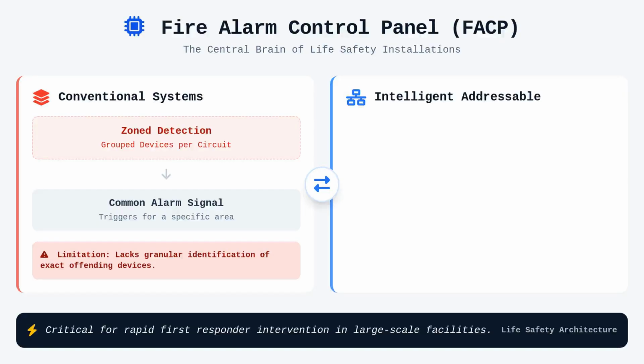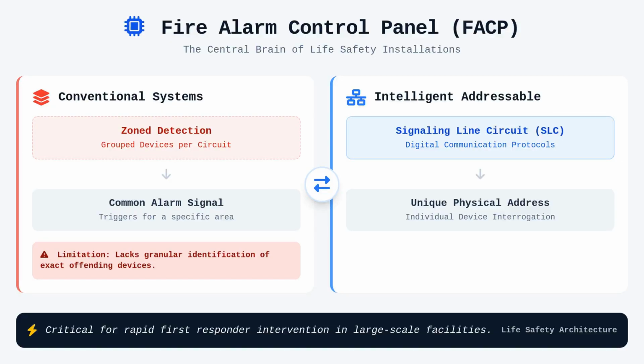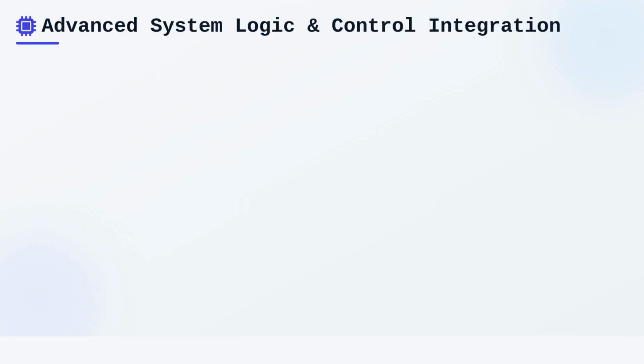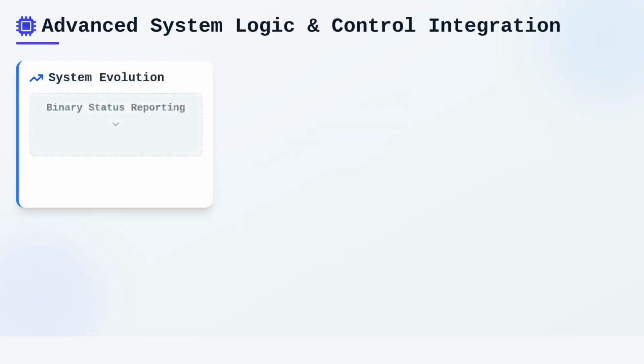This approach is conceptually simple, but presents limitations in large-scale facilities where pinpointing an emergency is critical for rapid first responder intervention. Conversely, intelligent addressable systems utilize a signaling line circuit, commonly referred to as an SLC, which employs digital communication protocols to interrogate individual devices. Each detector or module on an SLC has a unique physical address, allowing the FACP to monitor the health, status, and precise location of every component on the loop through continuous polling algorithms.